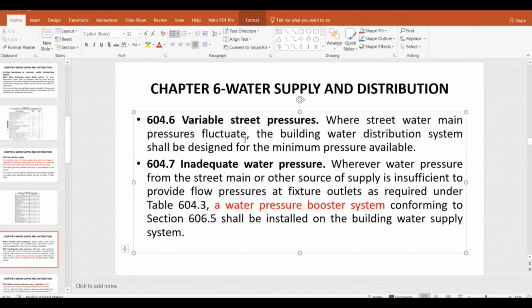Where street water main pressure fluctuates, the building water distribution shall be designed for the minimum pressure available. So we have to make sure that the overall system's minimum sanitary fixture pressure is satisfied. Based on the overall project's sanitary fixtures, we will design the pump head calculation. Whenever water pressure is not sufficient, we will provide the booster pump.